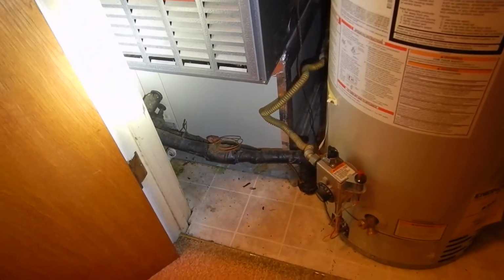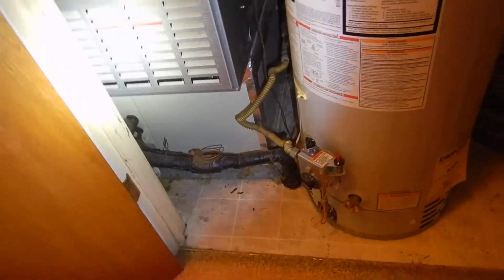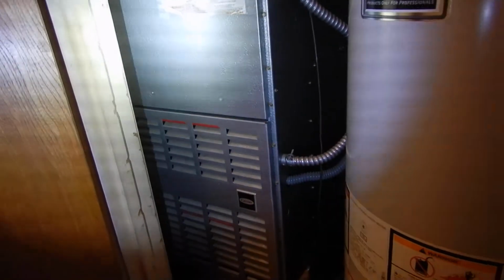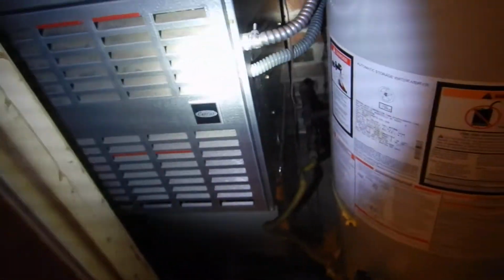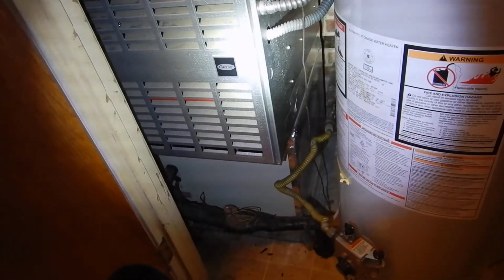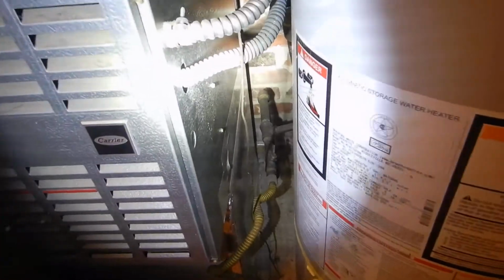And our evaporator coils are 32 years old. Looks like it's in pretty good shape. Looks like there's a pretty good history of maintenance, so things will look like that. Okay, but this equipment is aged. Not supposed to have a flexible gas pipe go into the furnace. They've changed the rules since then. Now it's allowed in certain circumstances, but not this gray plastic. So it's gray plastic improperly entering.